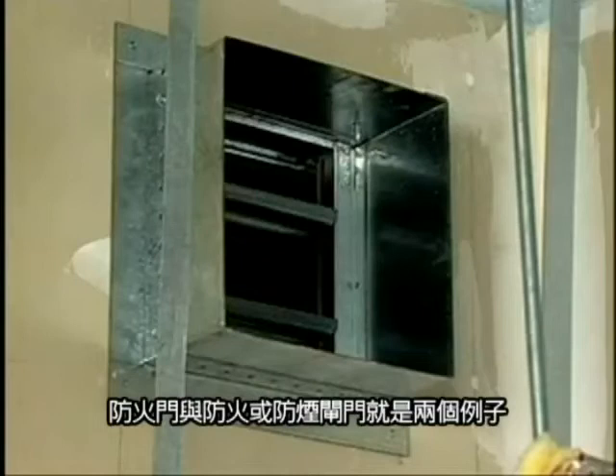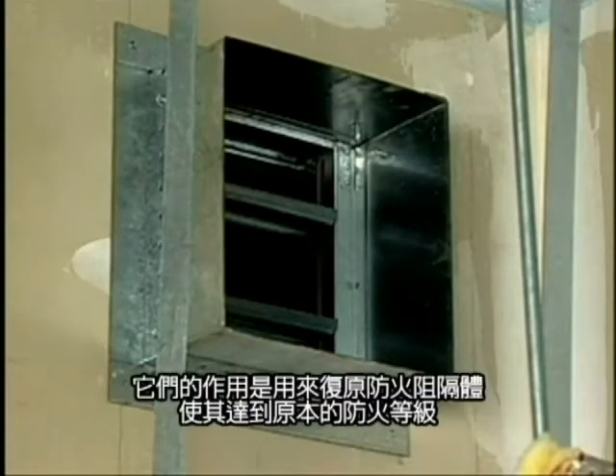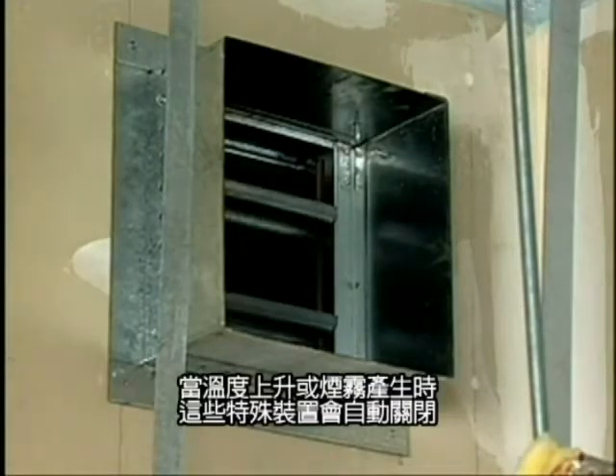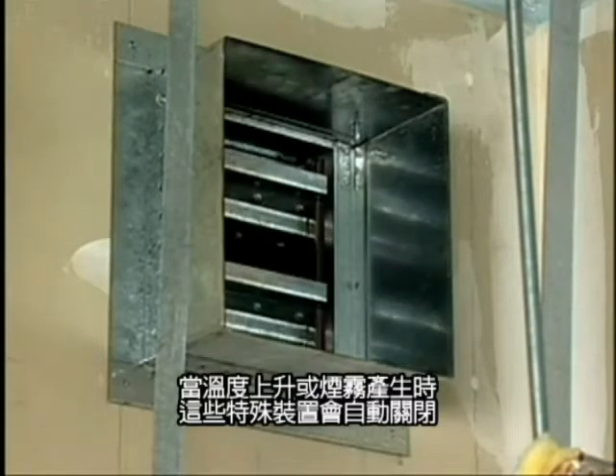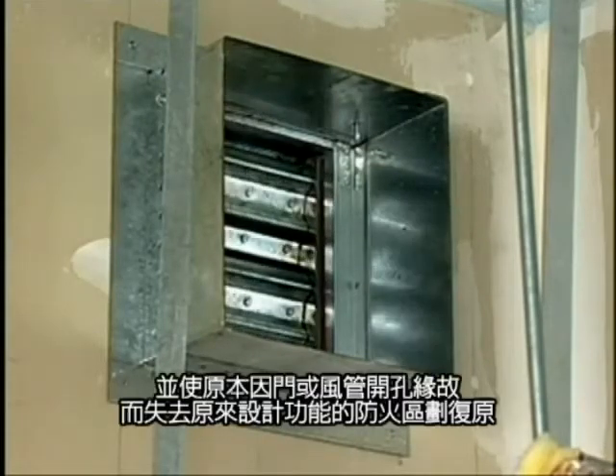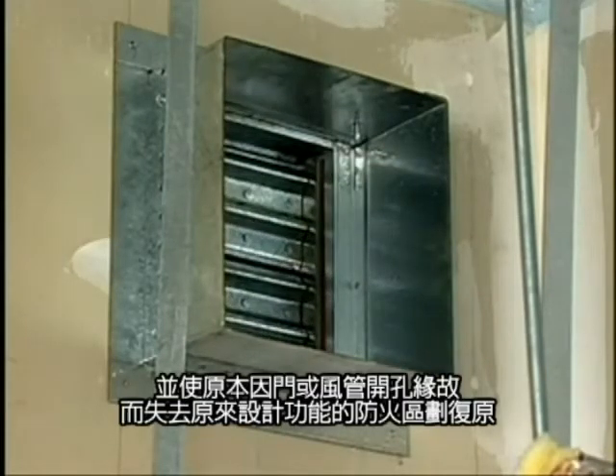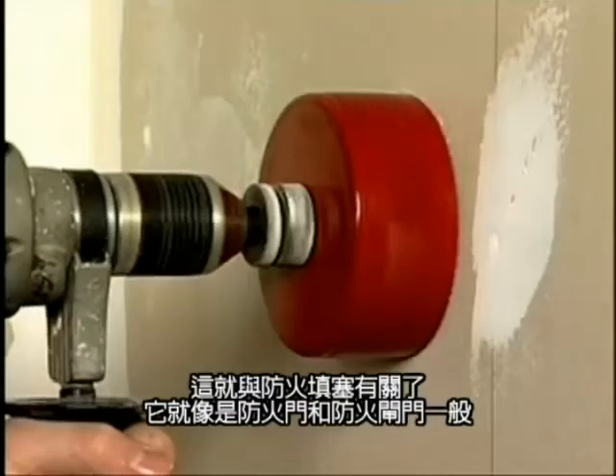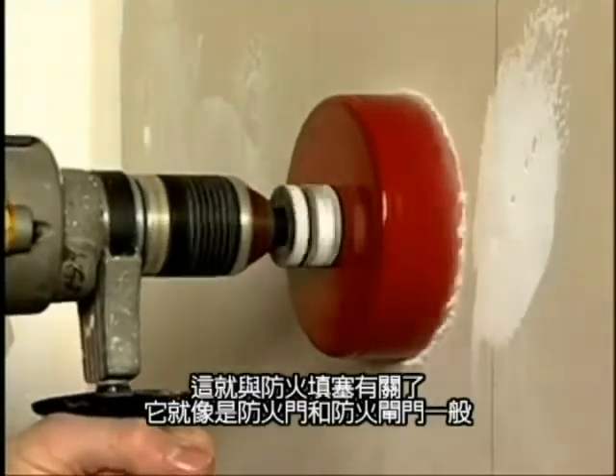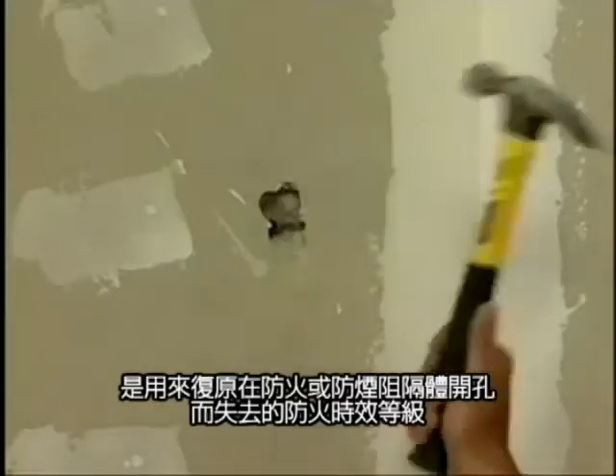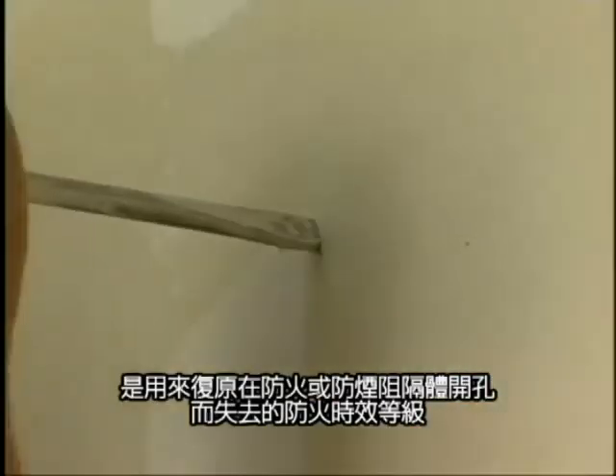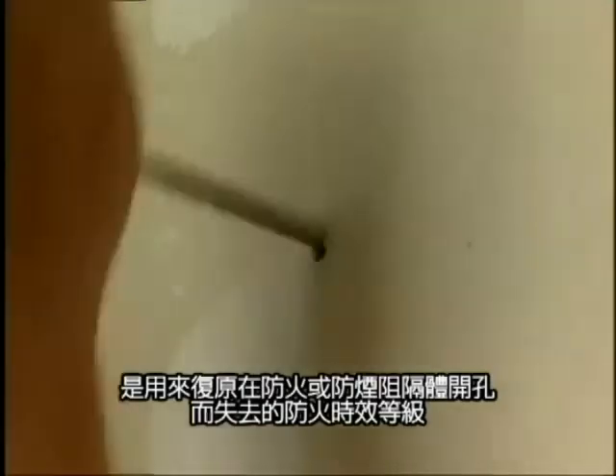Fire doors and smoke or fire dampers are two examples of devices designed to restore a barrier to its original rating. These specialized devices will close automatically in the presence of smoke and/or elevated temperatures and restore the compartmentation that was lost because of a door or duct opening. This brings us to Fire Stop, which, like fire doors and dampers, is designed to restore the hourly fire rating that was lost when an opening was created in a smoke or fire barrier.